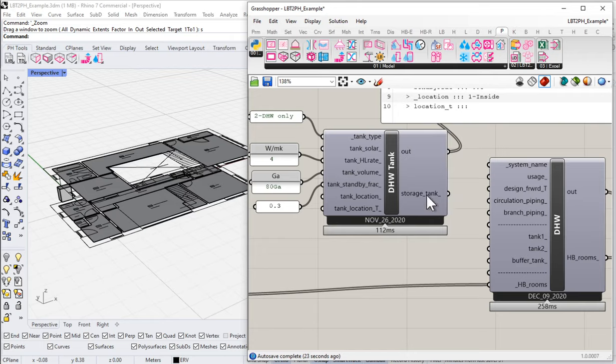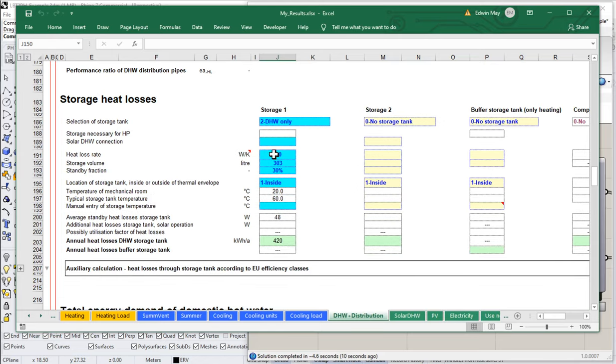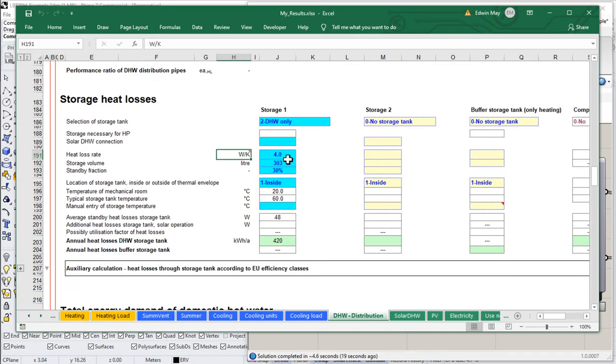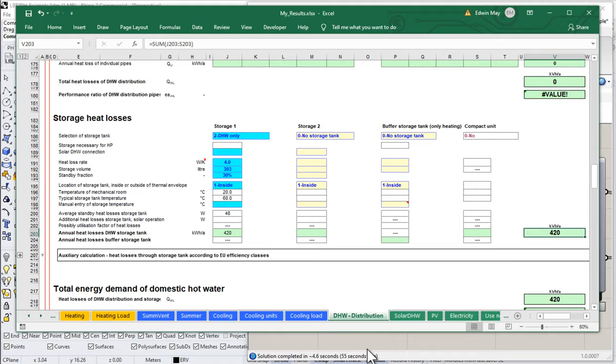As soon as I hook this tank up — taking the storage tank output and connecting it to tank number one in our system — once everything updates and all that data flows through, it should show up in our PHPP. Let's scroll down to the bottom — there's our first tank. Domestic hot water, 4 watts per kelvin, 302.8 liters, 80 gallons, 30% standby fraction, inside location. And zooming out, notice over here on the right we're now getting a heat loss value of about 420 kilowatt hours per year associated with that tank given those parameters. For our purposes, let's just say we have a single domestic hot water tank and leave it at that.